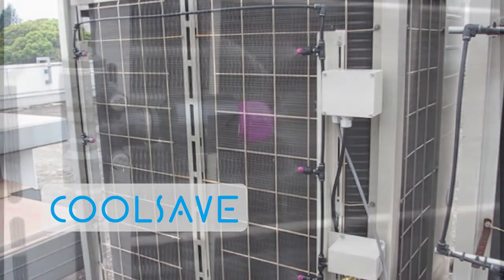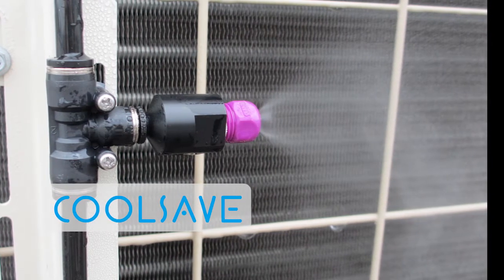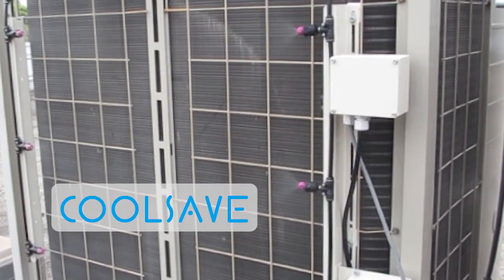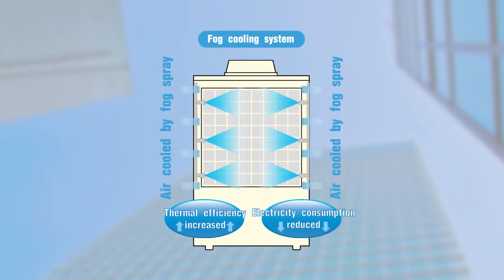The CoolSave system is designed to reduce electricity consumption by cooling outdoor units of building multi-air conditioning systems with a water fog. In hot summer weather, the thermal efficiency of outdoor units drops, causing electricity consumption to increase. CoolSave uses the evaporation cooling of fog to increase thermal efficiency and reduce electric consumption.